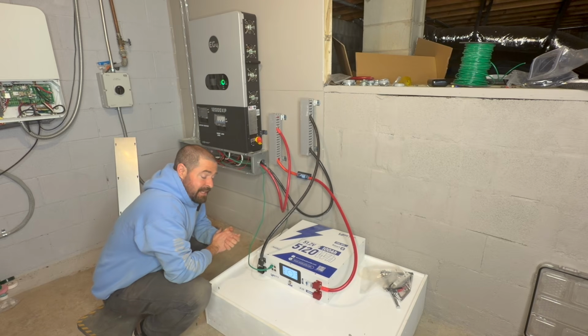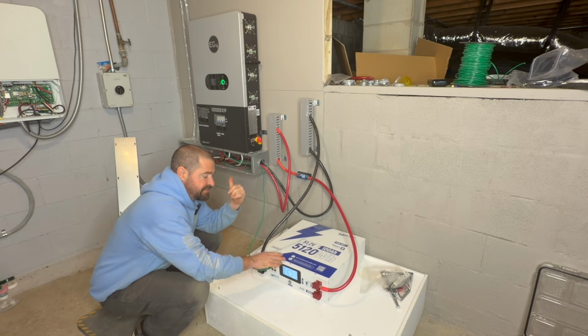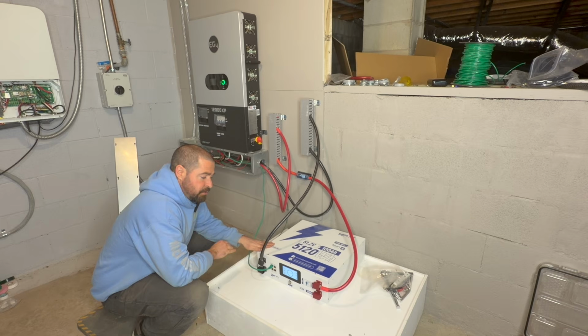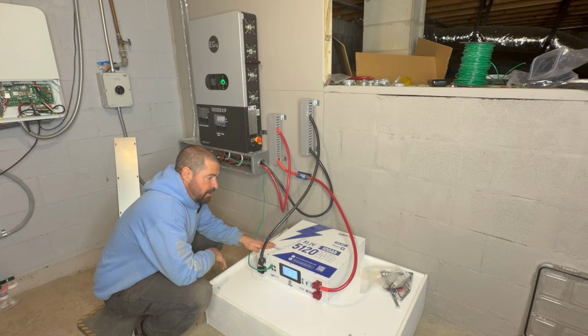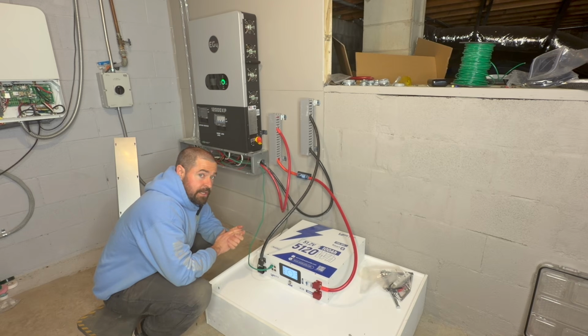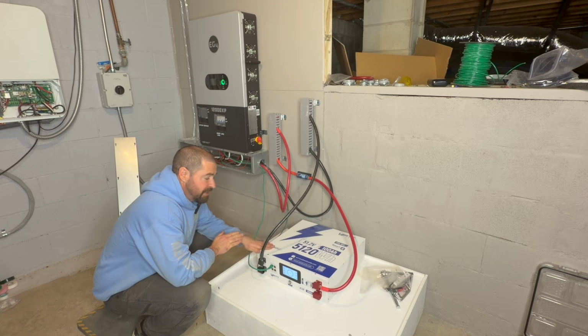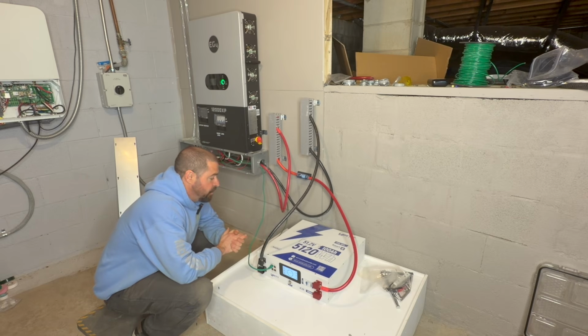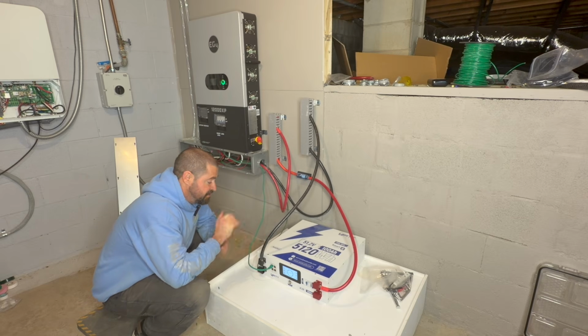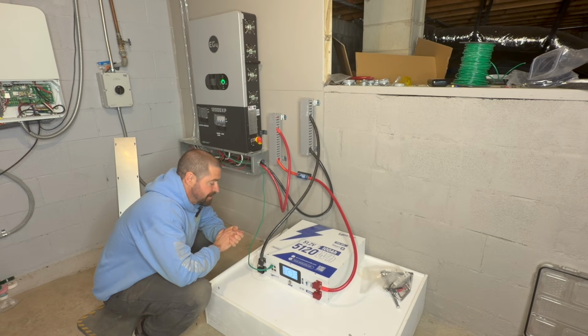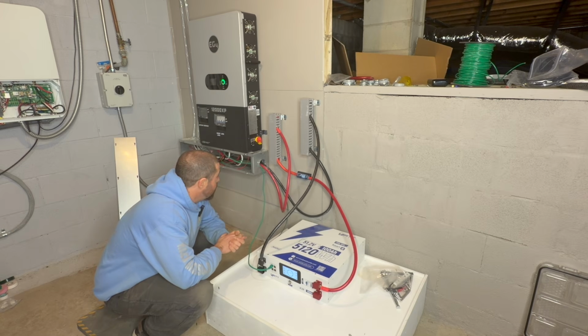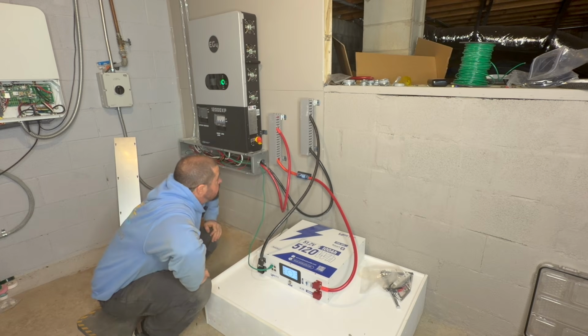And then I went ahead and set discharge and charge limits again, because this battery is way undersized for this inverter, and you're going to want at least 3. EG4 is suggesting at least 400 amp hours, so 3 to 4 batteries minimum is what you're going to want if you are installing these WattCycle batteries with your 12,000 XP at home. For the demonstration purposes of this video, I didn't have the chance to sink into buying a whole rack of these batteries, so I'm just getting one here to test it out and get a feel for it. Well, the discharge and charge currents are limited.